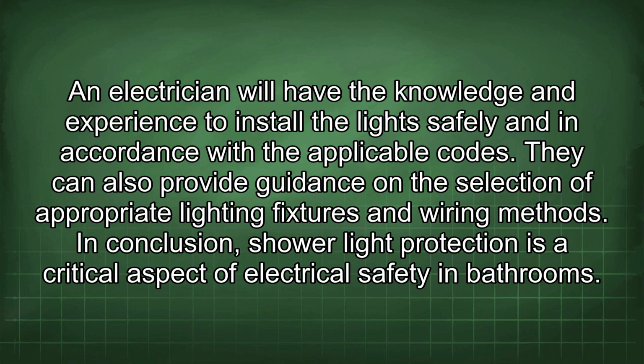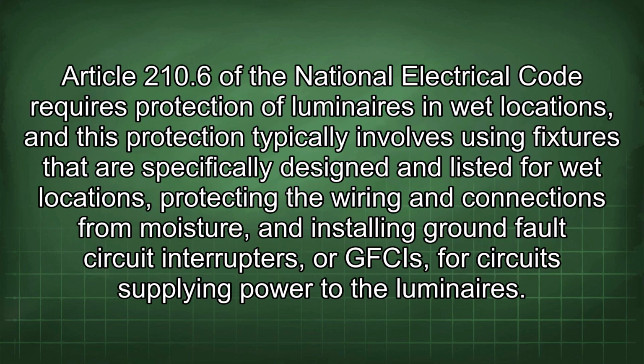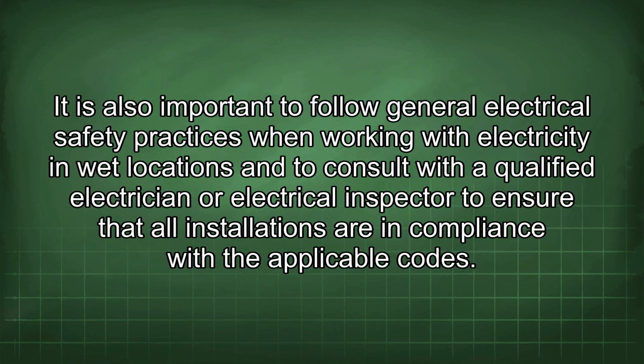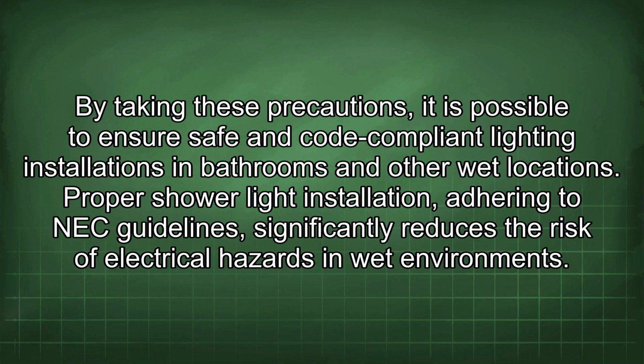In conclusion, shower light protection is a critical aspect of electrical safety in bathrooms. Article 210.6 of the National Electrical Code requires protection of luminaires in wet locations. This typically involves using fixtures specifically designed and listed for wet locations, protecting wiring and connections from moisture, and installing ground fault circuit interrupters, or GFCIs, for circuits supplying power to the luminaires. It is also important to follow general electrical safety practices in wet locations and consult with a qualified electrician or inspector to ensure compliance with applicable codes. By taking these precautions, it is possible to ensure safe and code-compliant lighting installations in bathrooms and other wet locations.